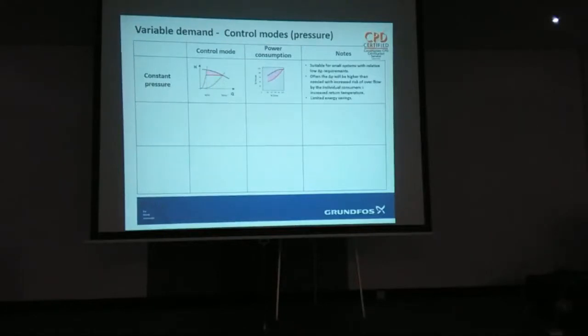These methods of control are standard terms within the industry. Constant pressure is used a lot, but it's only constant pressure at the point of measurement. In this particular example, it's across the pump. So the pump maintains, let's say, for example, 100 kPa at maximum flow or minimum flow. The valve closes, the system curve goes up and down like that. The pump just maintains a constant pressure at the pump. Or if you're measuring across the manifold, with a couple of pumps on, across that manifold.